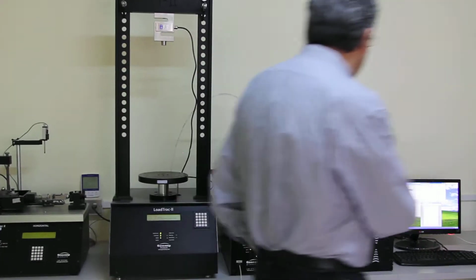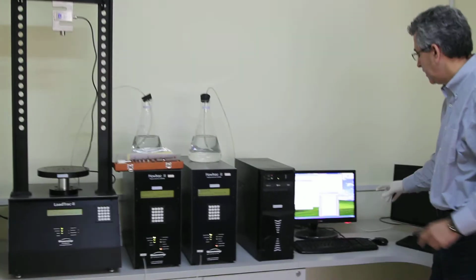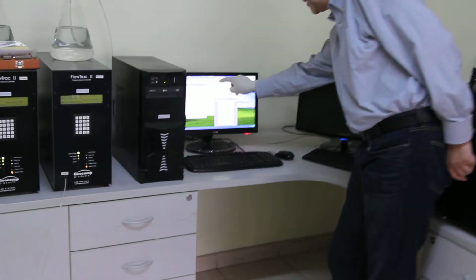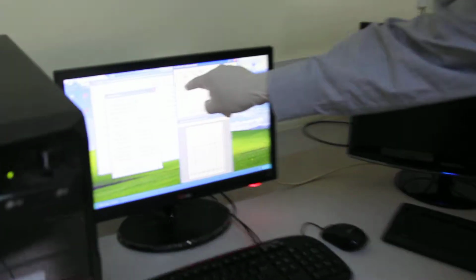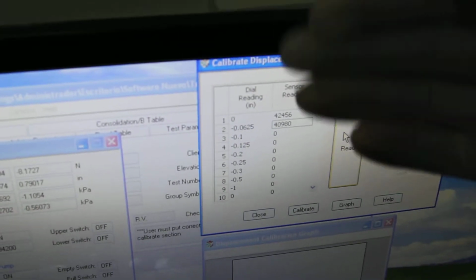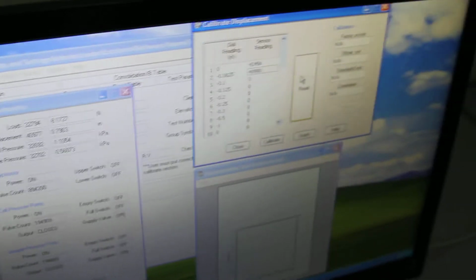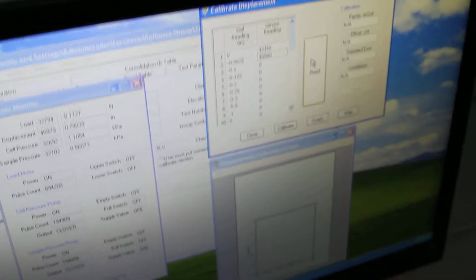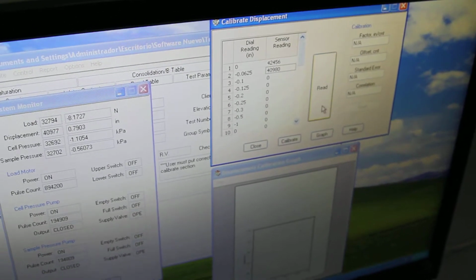Now I'm going to go to the software and look at my dial reading, which is 0.0625 inches. That corresponds to my first gauge block. And what I'm going to do is a read. So now it's going to read the displacement from what was 0, which was our reference. You notice here that the numbers are negative, because we are doing the calibration in a descending order, so we can get a calibration factor that is positive.